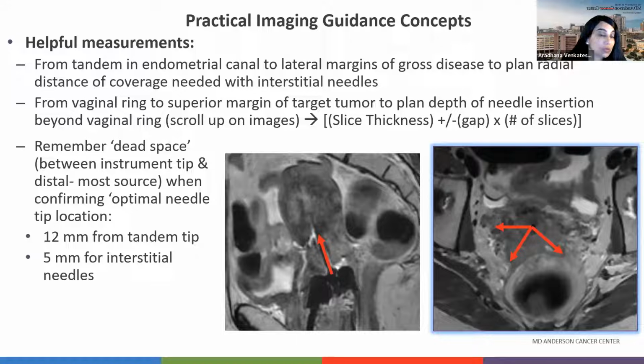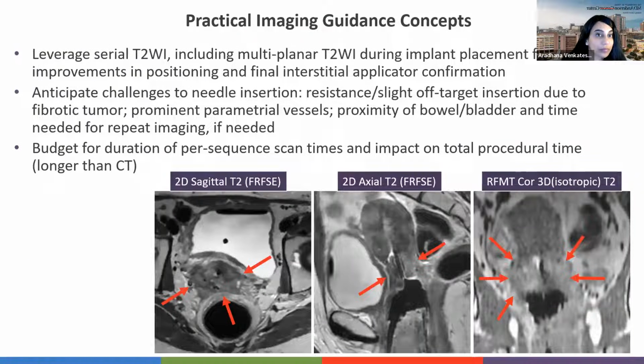Remember as well that there is a relative, quote unquote, dead space between your instrument tip and what will be your distal-most source when confirming the optimal tip location where you want your needles to end up. So that's 12 millimeters from the tandem tip and 5 millimeters for your interstitial needles. Next slide. And so during the procedure, do make abundant use of your high resolution T2 weighted images, including, as mentioned, the multiplanar acquisitions that you can acquire as shown on this slide, while you're adjusting and inserting additional needles if that is deemed beneficial based upon your initial imaging data sets.